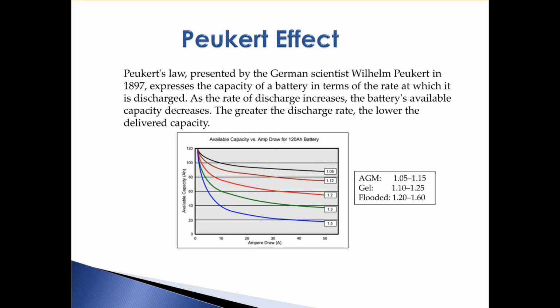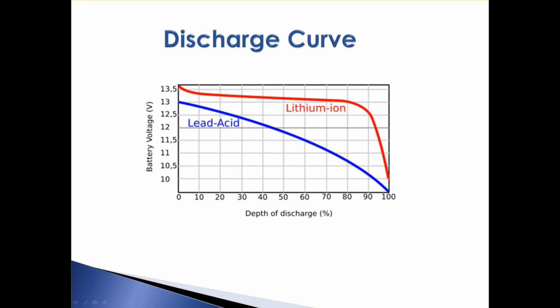So this is a big drawback to lead acid batteries, particularly when you use them in high load applications like driving an inverter, where you might be pulling 100, 200, 300 amperes out of the battery to run the inverter when it's running up at its rated load. The discharge curve looks like this. The lead acid battery starts to lose voltage about as soon as you start pulling energy out of it. And it will discharge down to under 10 volts by the time it's completely discharged.